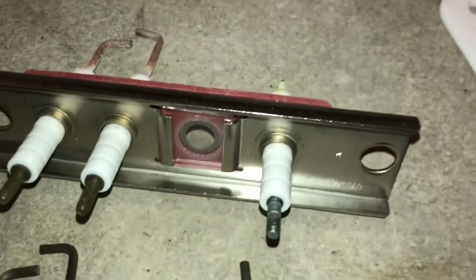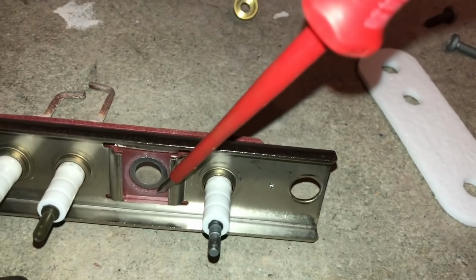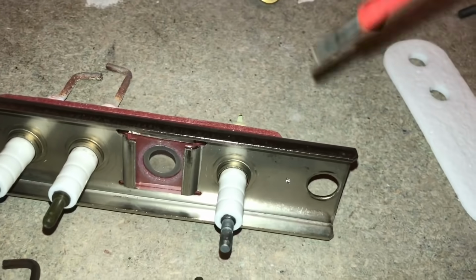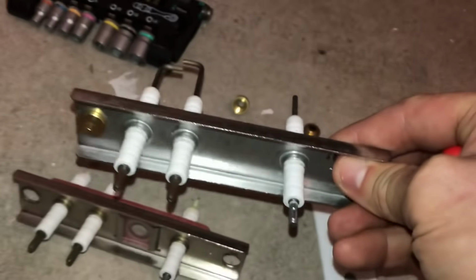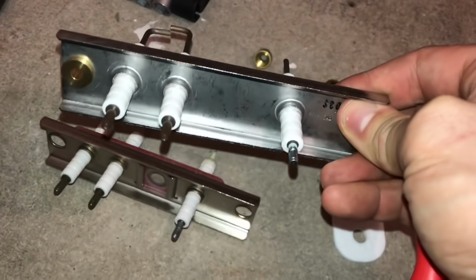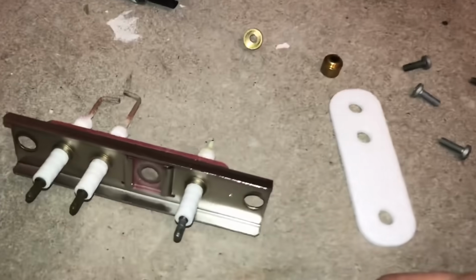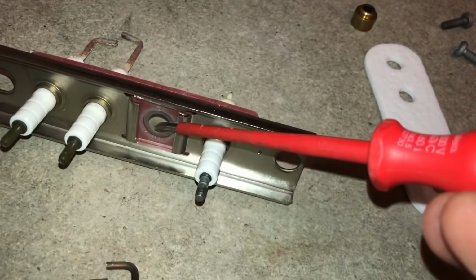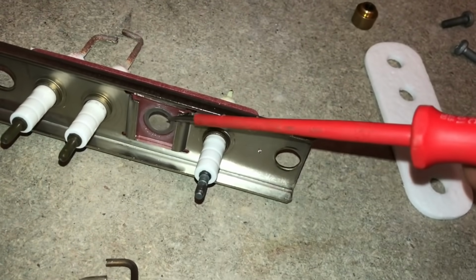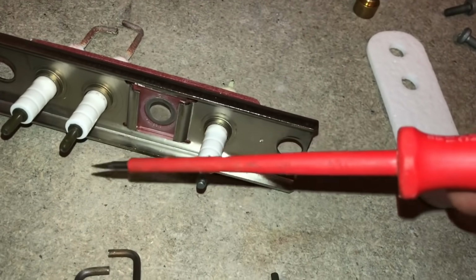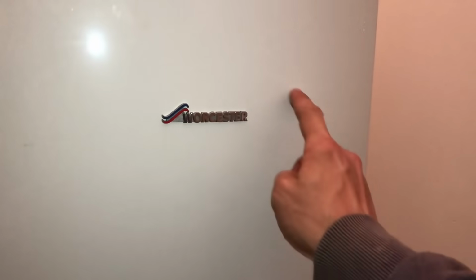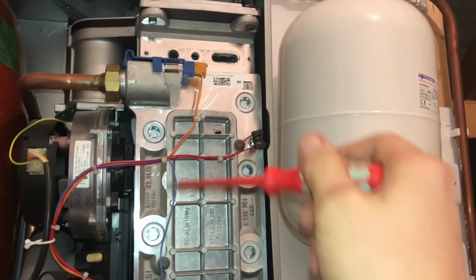You can see here, we've got this viewing eye here. Now Worcester have actually superseded this part with this one, which is the replacement. You can see that viewing window's gone. Because what would happen is the glass would crack, and then the lit gas would shoot out of here, and it would burn all the front cover of the boiler. You'd have a big burn mark there, and it would also ruin all these cables and things.